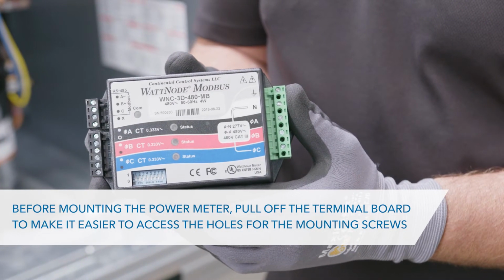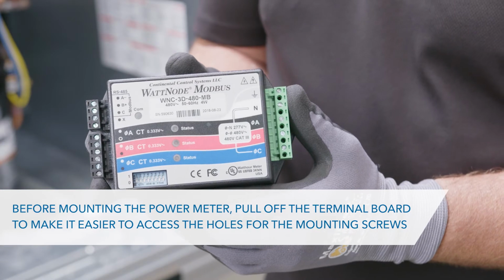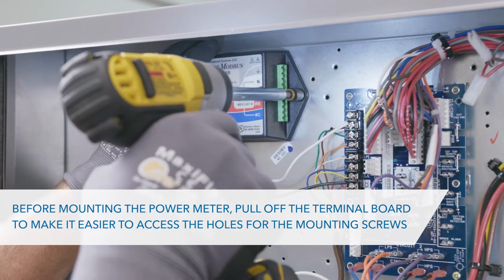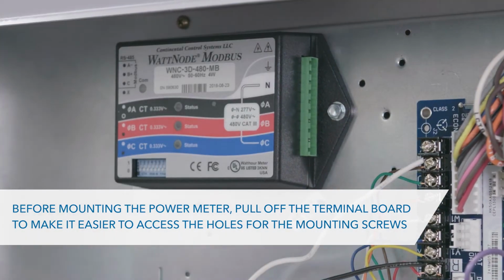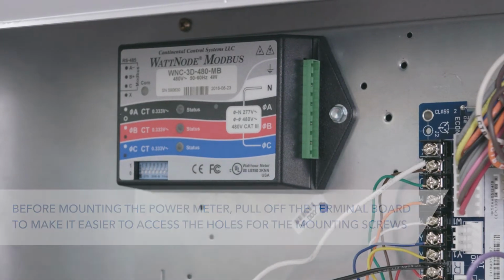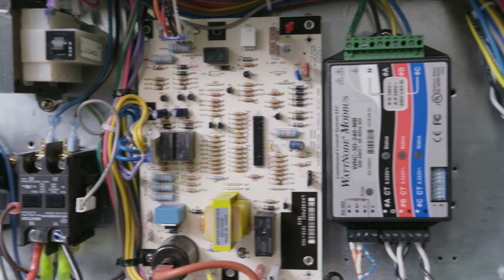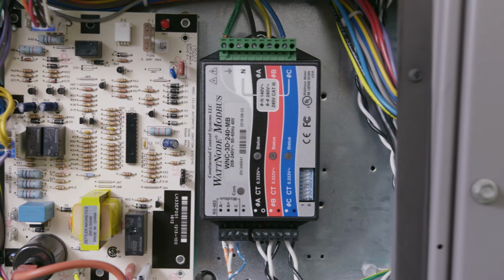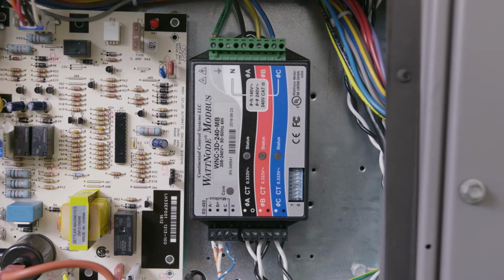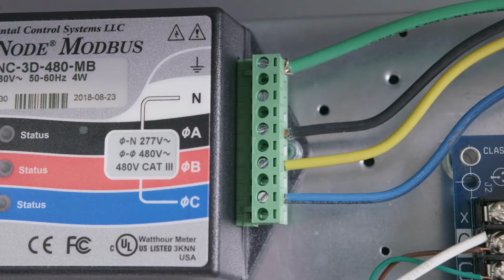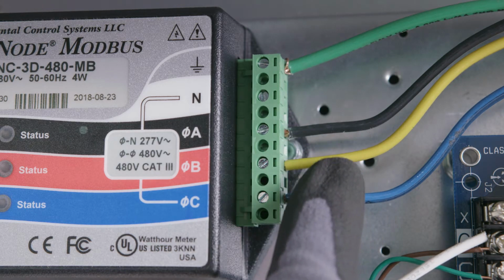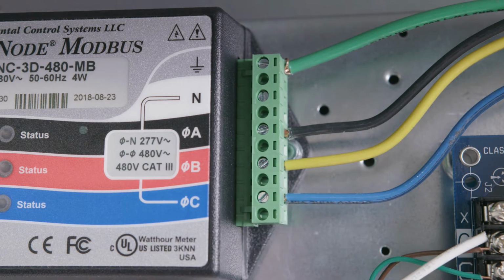You need to find a location to mount this. Typically the best spot is in the HVAC unit's control panel, or you may consider mounting it in the fan section. On a smaller unit, you might have to mount it vertically. You can mount it either vertically or horizontally. It doesn't matter as long as you have ample room to run the control wiring on both sides. On the right-hand side, you have terminals for the A, B, and C phases of power, which need to be connected to the line voltage.